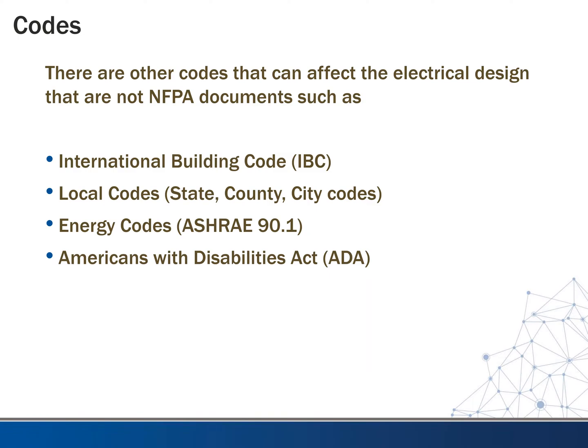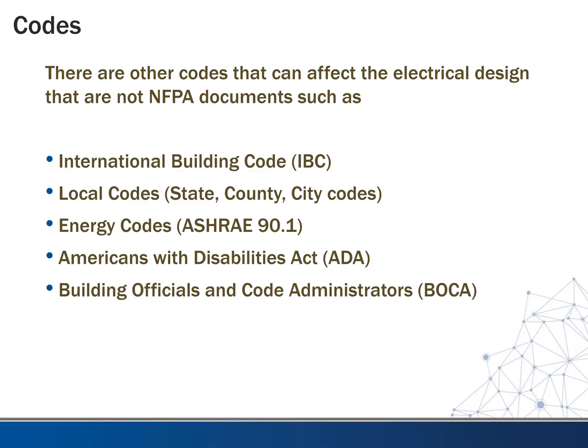Another one is the Americans with Disabilities Act. This can govern our work as well. If we have a building that falls under ADA requirements, probably the primary way it affects us is if there are any wall sconces — fixtures mounted to the wall — they can't protrude out more than four inches; if they're more than four inches, that's not ADA compliant. There's also the Building Officials and Code Administrators, and some local authorities adopt aspects of those documents. One example is they have a requirement that pull stations or fire alarms have to be within five feet of all egress doors.